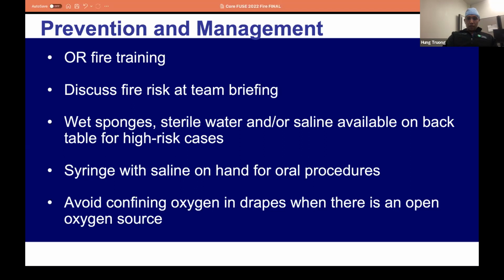If there's a high risk case, avoid confining oxygen in the drape. Make sure oxygen levels don't accumulate in compartments around the drapes, especially near the anesthesia side, to prevent one of the ignition sources that can cause an OR fire.